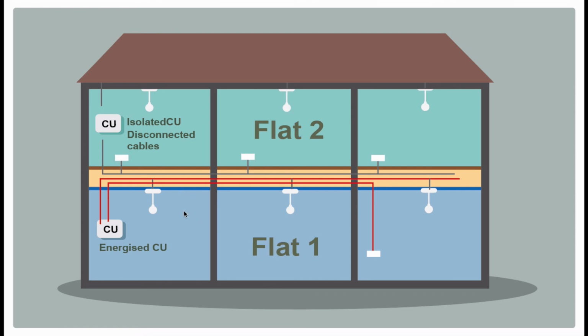But don't forget, what's your floor is their ceiling, and they're going to have cables in the same void, possibly, which is still live. So even though you think everything's dead in your flat, there's still going to be live conductors from downstairs in the same void as your cables. So you always have to take good care, and it's sometimes difficult to know what cables are doing what. You've got to kind of follow things. You only know if something's dead when you can see both ends of it. If you're putting something out, you've got to know for a fact that it's dead. Don't go cutting through cables thinking it's dead, because this might be energized from downstairs.